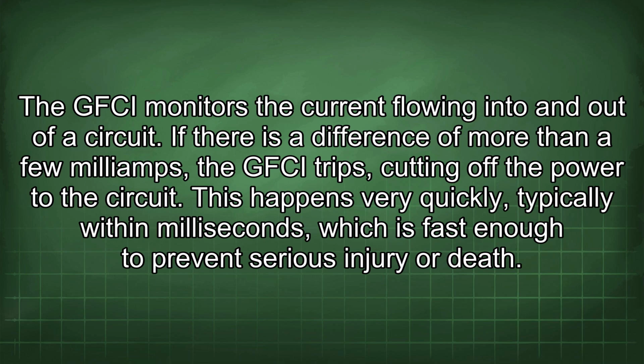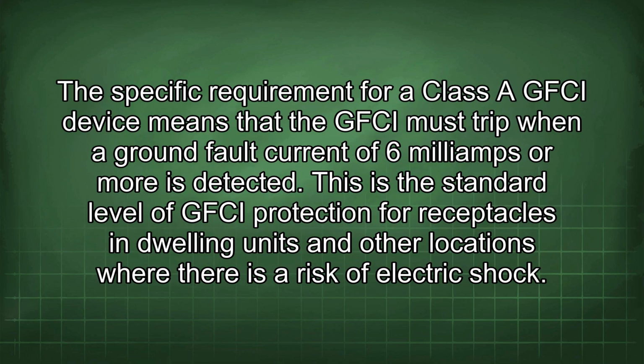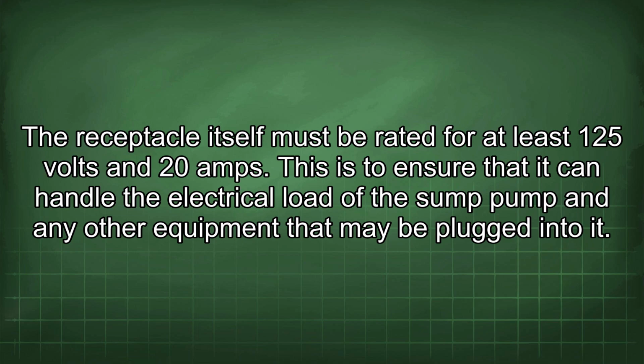If there is a difference of more than a few milliamps, the GFCI trips, cutting off the power to the circuit. This happens very quickly, typically within milliseconds, which is fast enough to prevent serious injury or death. The specific requirement for a Class A GFCI device means that the GFCI must trip when a ground fault current of 6 milliamps or more is detected. This is the standard level of GFCI protection for receptacles in dwelling units and other locations where there is a risk of electric shock. The receptacle itself must be rated for at least 125 volts and 20 amps.